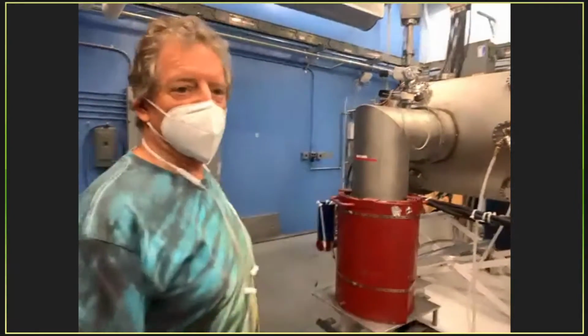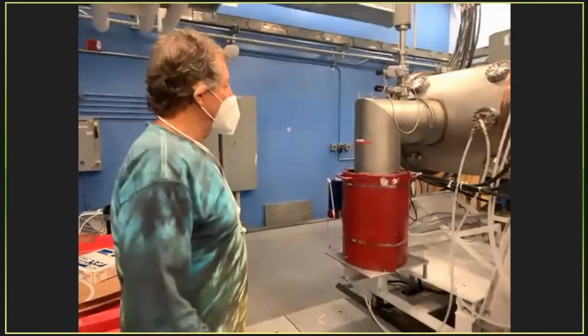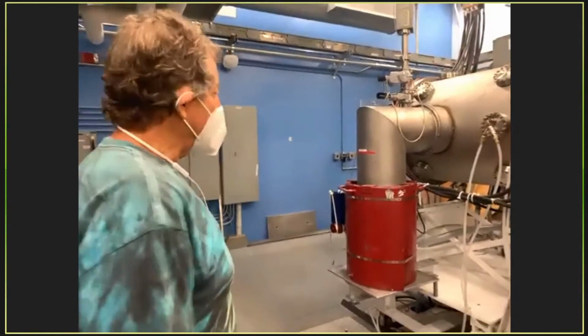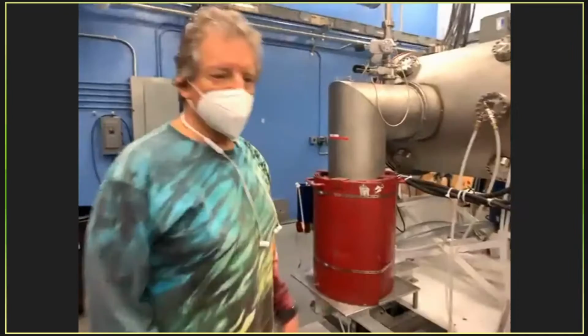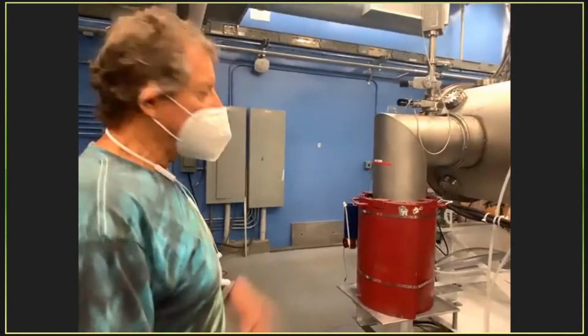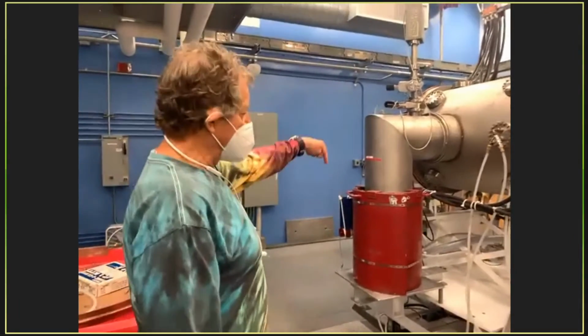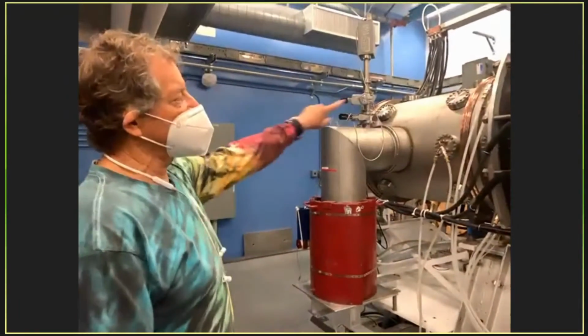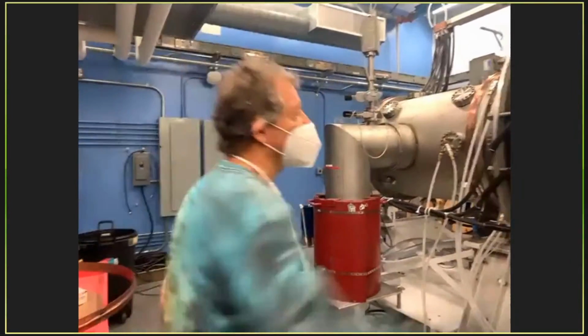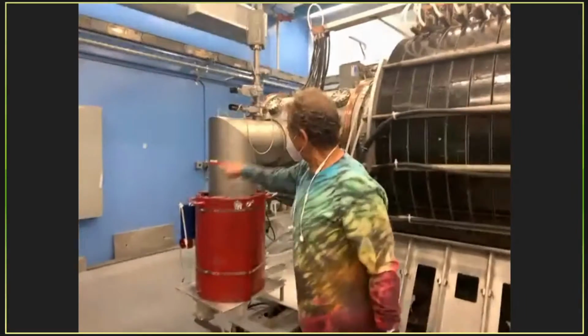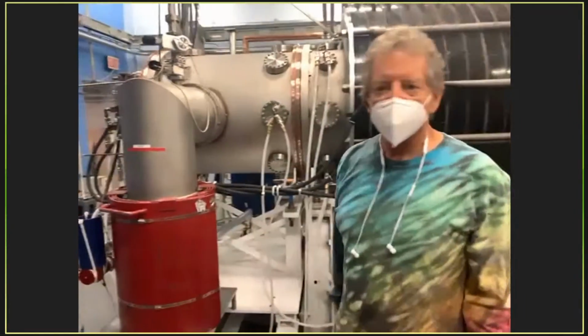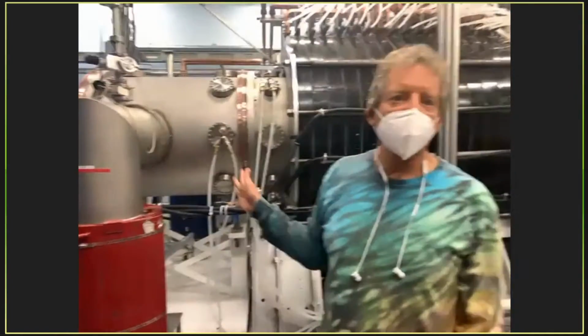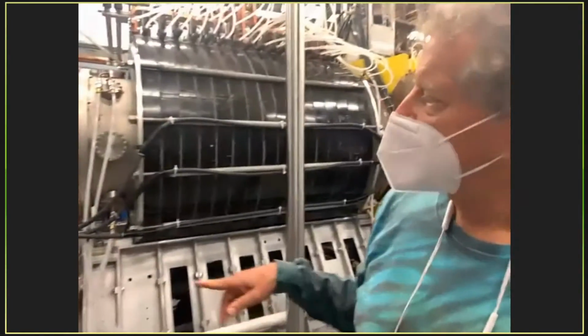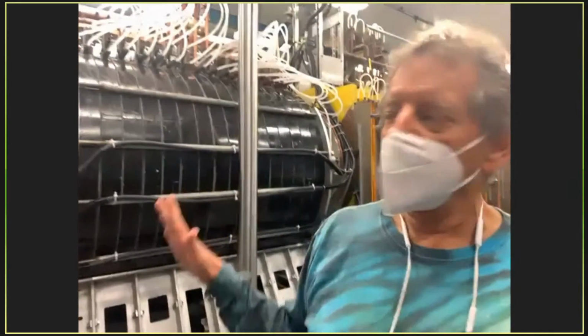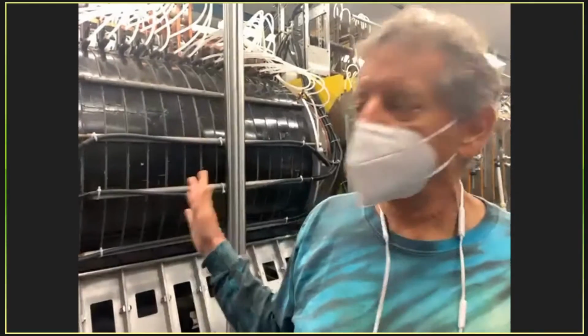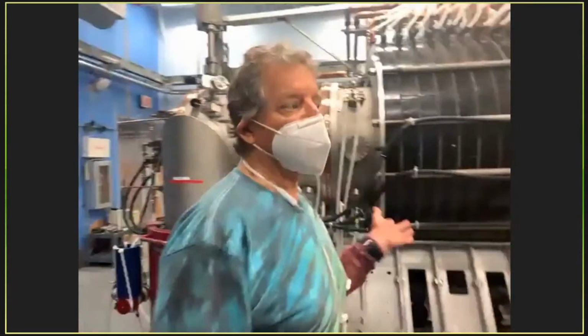So this thing over here doesn't look like much. It's a vacuum pump. There are 4 of them on the machine. And inside this pump are spinning blades, like jet engine blades. They're spinning 40,000 times a minute. And that spinning action, if a particle, which is bouncing around the machine, boing, boing, boing, goes into this tube, it gets caught in the blades and expelled from the machine. And that's how we keep a vacuum. So it's 4 of these things. The vacuum conditions are about, if we remove the gas that's making the plasma, about one billionth of an atmosphere. So kind of like in space.